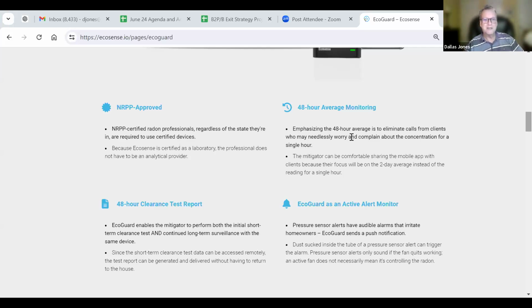It's a great place. And then I had a question about the Radon Eye Pro. Does it come calibrated, or do I need to send it out to the lab? Okay, Jim, that's a question that is interesting just for this reason, because you said you took the NRSB test. If you had taken the NRPP, and I know it probably didn't seem to make any difference at the time you chose the exam, then they accept our original calibration certificate from our chamber in South Korea, and they're quite happy with it.